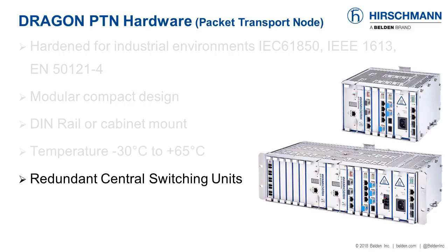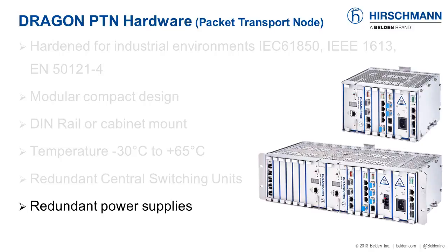Industrial networks are often mission critical and failure is not an option, so it's important that essential hardware components are duplicated. The central switching unit is the core processor for the Dragon PTN, and most chassis support redundant central switching units. Redundant power supplies are also available — these power supplies are hot swappable, meaning they can be exchanged while the device is running. Power input options include 18 to 60 volts DC, 88 to 300 volts DC, and 90 to 264 volts AC.